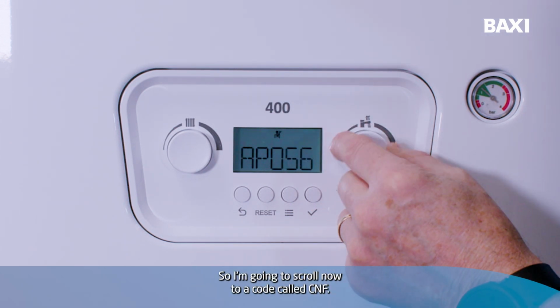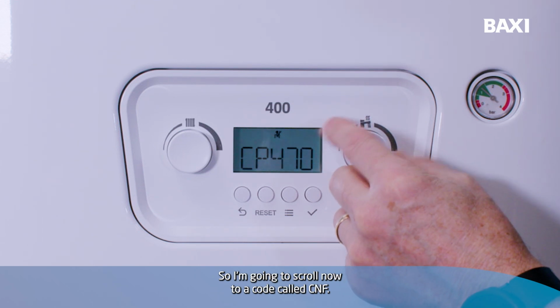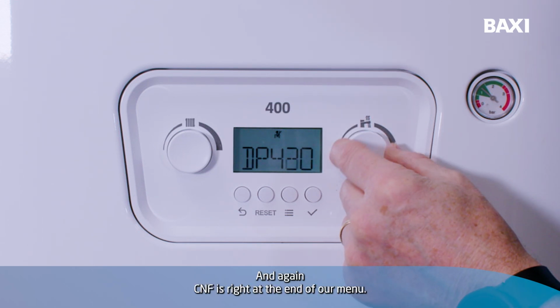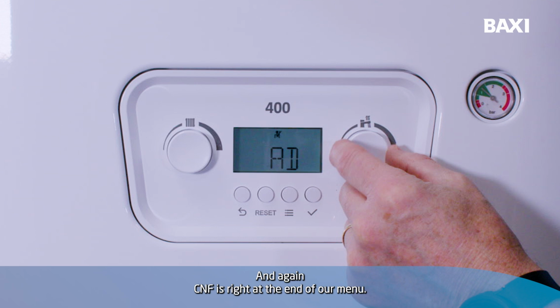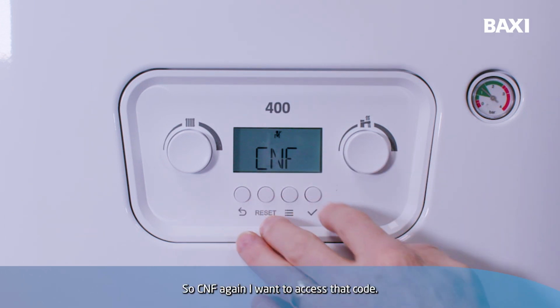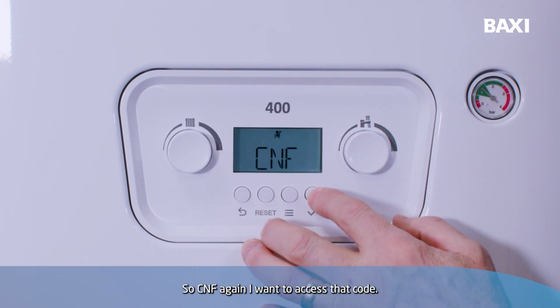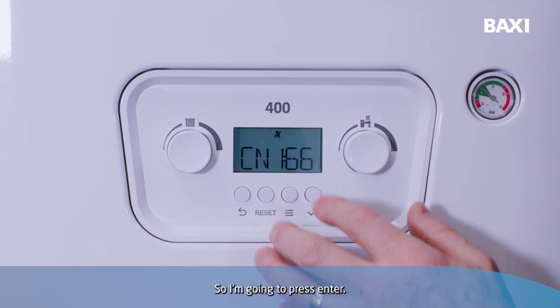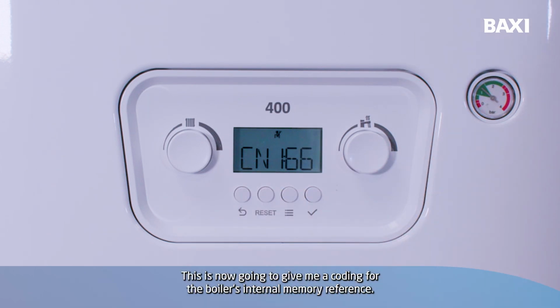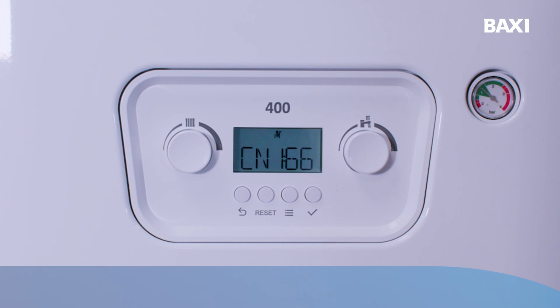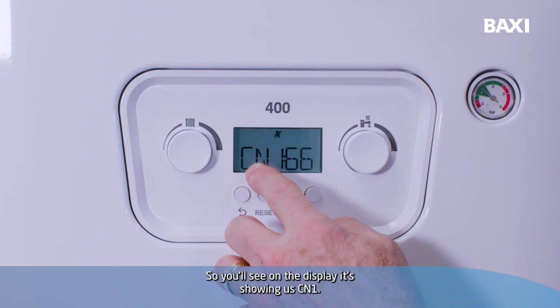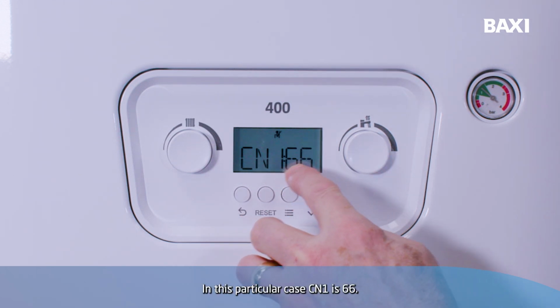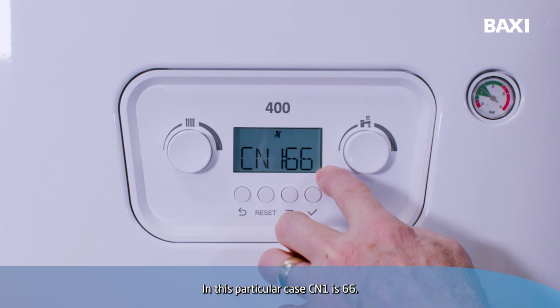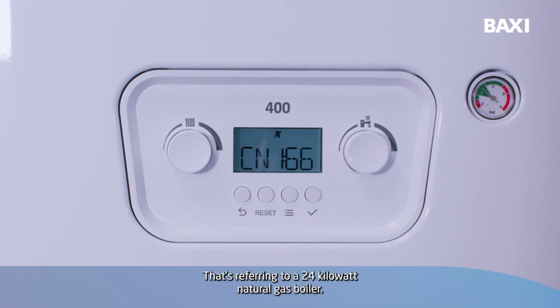So I'm going to scroll now to a code called CNF. And again, CNF right at the end of our menu. There it is. So CNF, again, I want to access that code, so I'm going to press enter. This is now going to give me a coding for the boiler's internal memory reference. So you'll see on the display, it's showing us CN1. In this particular case, CN1 is 66. That's referring to a 24 kilowatt natural gas boiler.